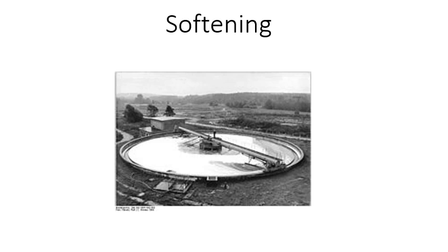Permanent hardness is non-carbonate hardness. In the state of Florida, where I'm at, you have calcium sulfate, calcium chloride, magnesium sulfate. Permanent hardness removal requires both excess lime and soda ash. Non-carbonate hardness is from magnesium sulfate, magnesium chloride, calcium chloride, and calcium sulfate. Other parts of the country can have nitrates and silicates, which would need ion exchange versus softening. Total hardness equals calcium plus magnesium hardness.